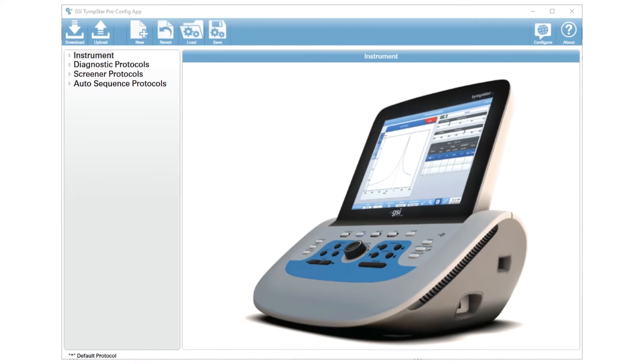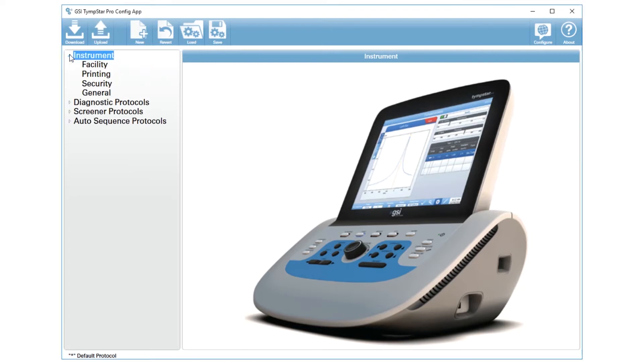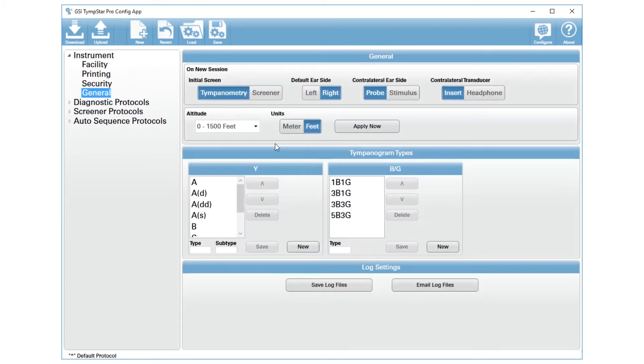You can change the reporting ear on the contralateral reflexes from the probe ear to the stimulus ear using the GSI configuration application. When you open up the GSI TympStar Pro Config app, you will press Upload to bring over the settings from the TympStar into this program. Then you will go into Instrument and the General selection, and this is where you will find your contralateral reflex reporting options.